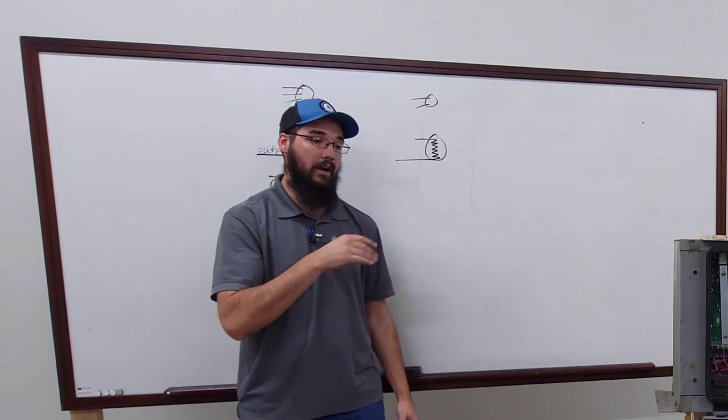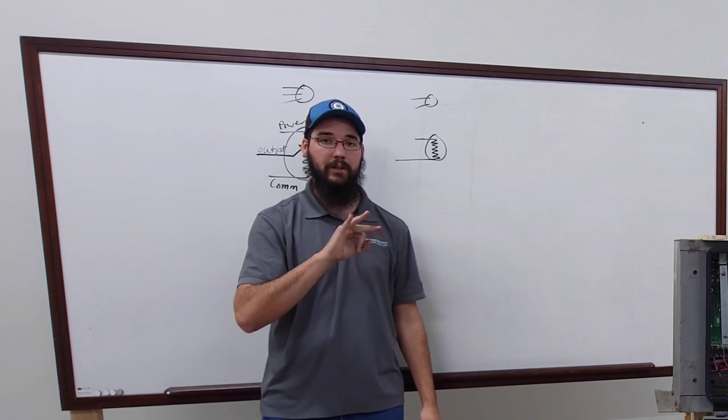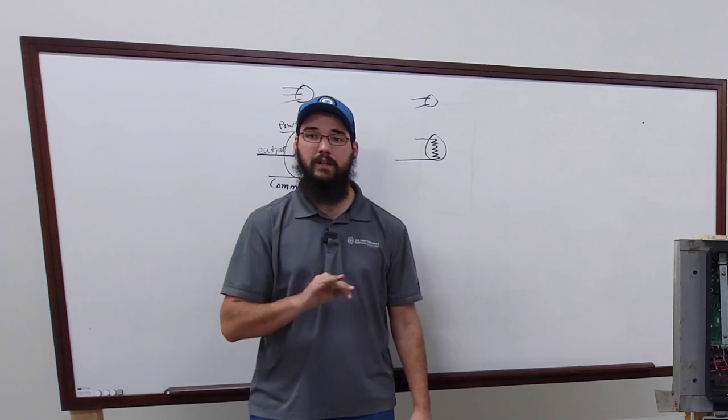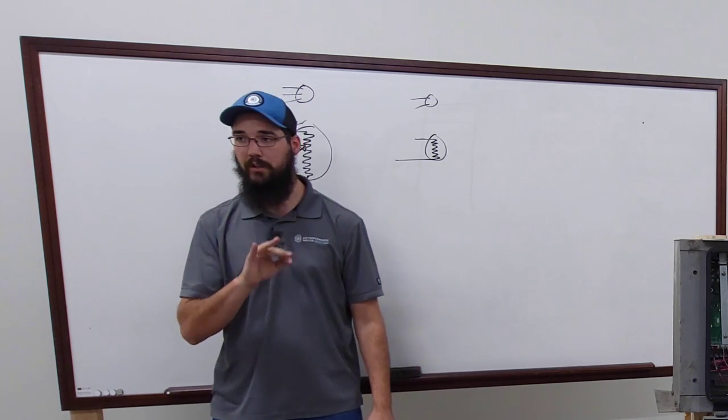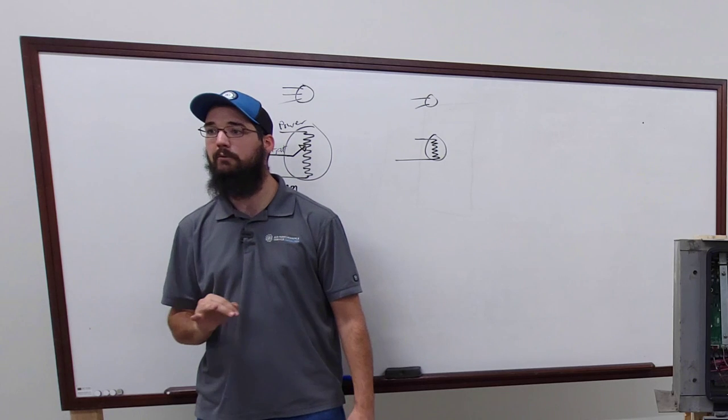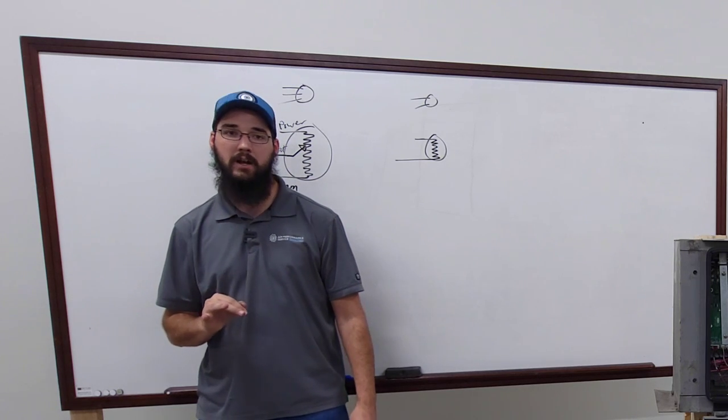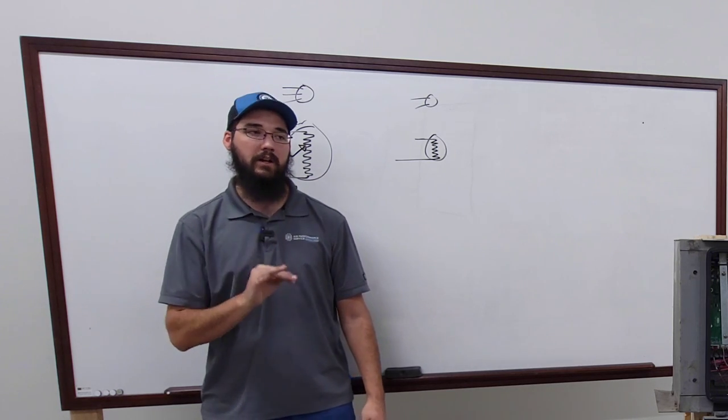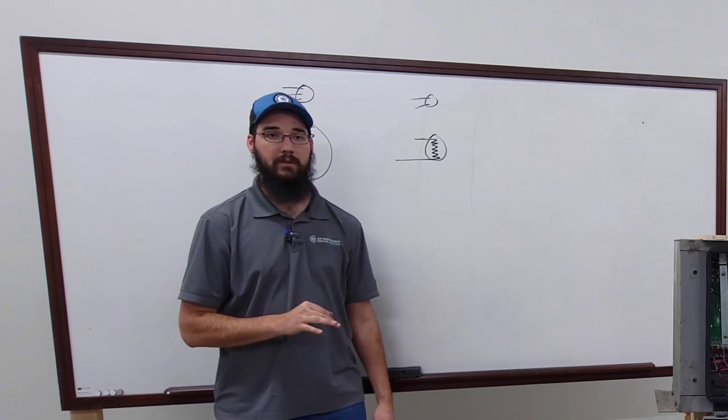Because what will happen on components like these is as they begin to fail, they fail at an exponential rate. Once they start to show early signs of wear, it may have taken five years to get there, but it's going to take three months to go the rest of the way and finally crap out. Two degrees is the standard — if you see it outside that range, plus or minus, recommend replacement.